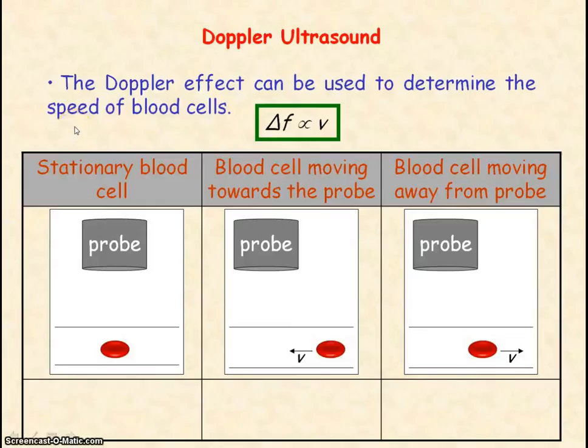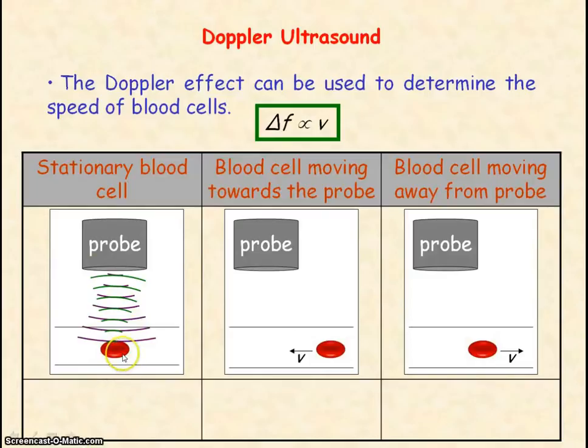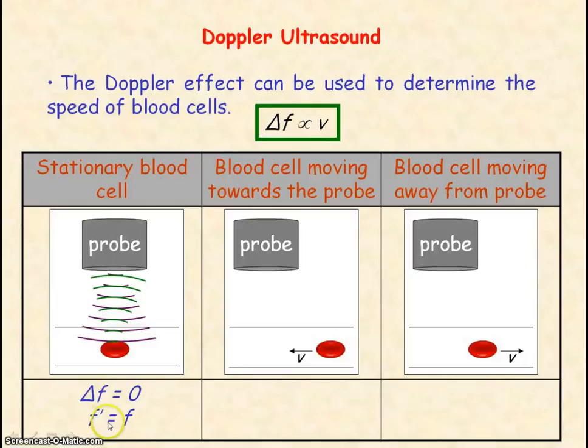The Doppler effect can be used to determine the speed of blood cells, and the Doppler shift — the change in frequency — will be directly proportional to the speed of the blood cells. The ultrasound probe directs ultrasound towards blood cells where they get reflected back to the probe. If the blood cells are stationary, there would be no Doppler shift, no change in frequency, and so f prime, the frequency of the reflected ultrasound received by the probe, would equal f, the original frequency emitted.